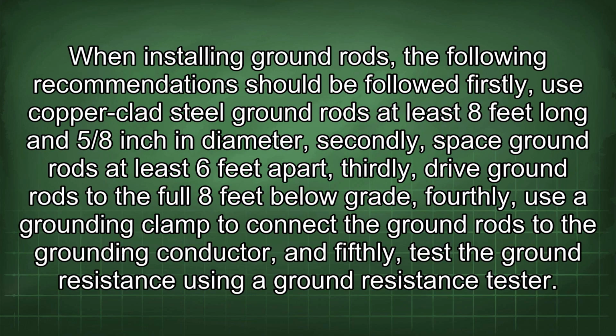When installing ground rods, the following recommendations should be followed. Firstly, use copper-clad steel ground rods at least 8 feet long and 5/8 inch in diameter. Secondly, space ground rods at least 6 feet apart. Thirdly, drive ground rods to the full 8 feet below grade. Fourthly, use a grounding clamp to connect the ground rods to the grounding conductor. And fifthly, test the ground resistance using a ground resistance tester.